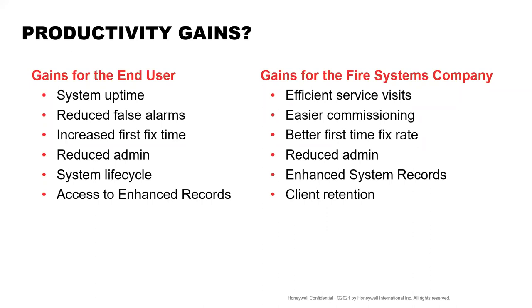Easier commissioning. So from your perspective, you guys who are dealing generally, I would guess, more with new builds and whatever, it's much more easy from a commissioning perspective when the system's gone in and you're actually walking around and testing it before the building's handed over. It makes it much easier. And once again, all the reports that go with the commissioning are all automatically generated. Better first time fix rate, because you can see what's going in and where.